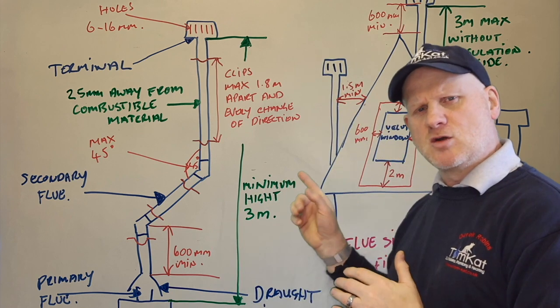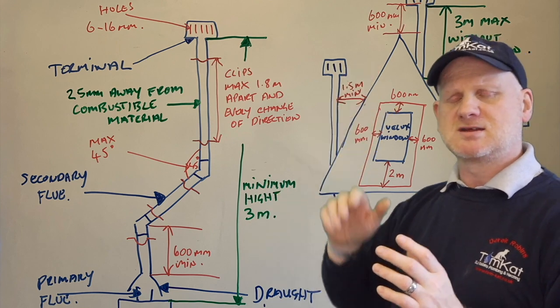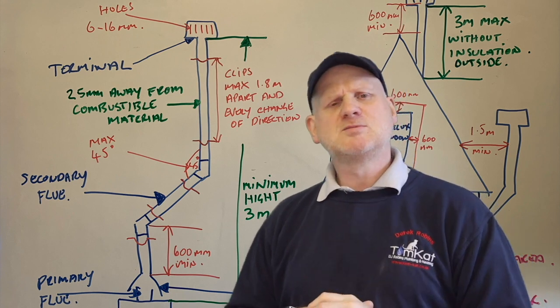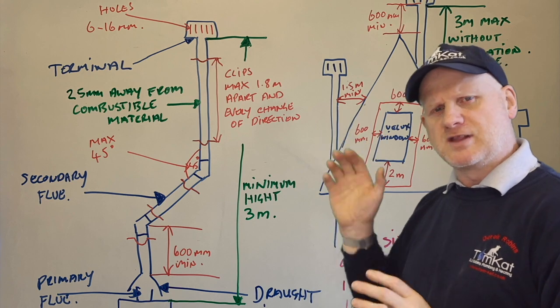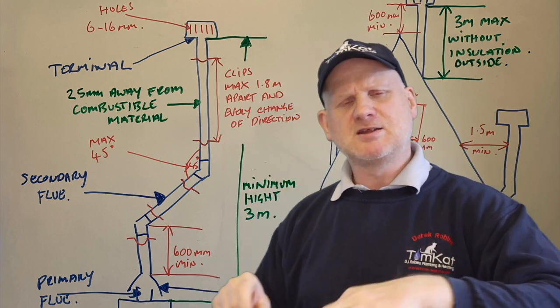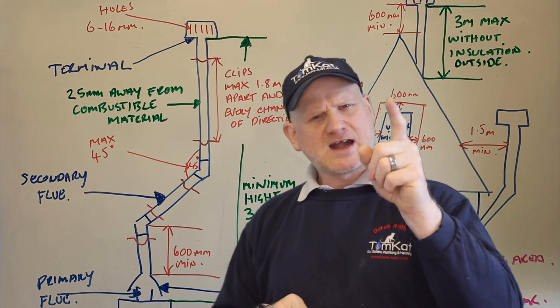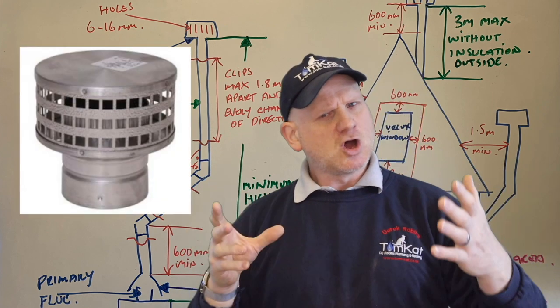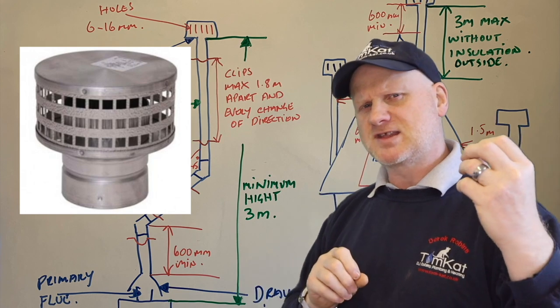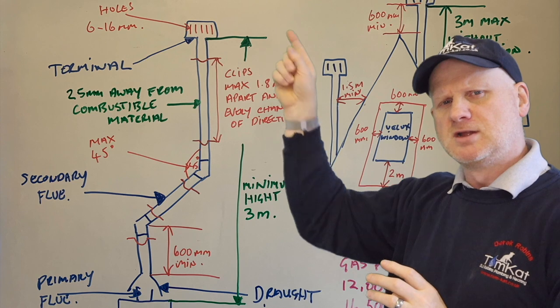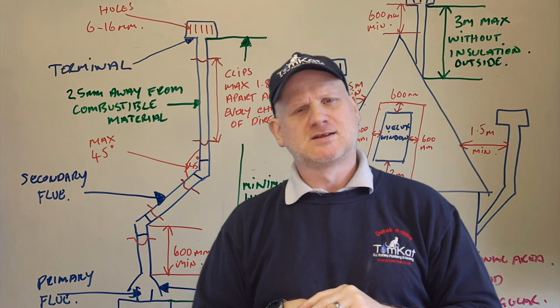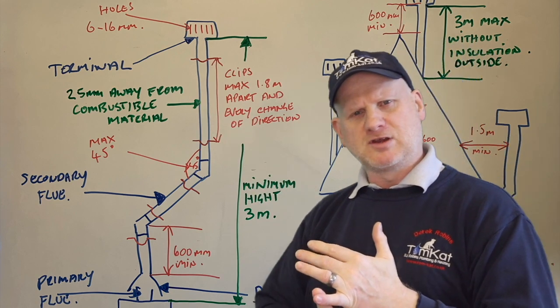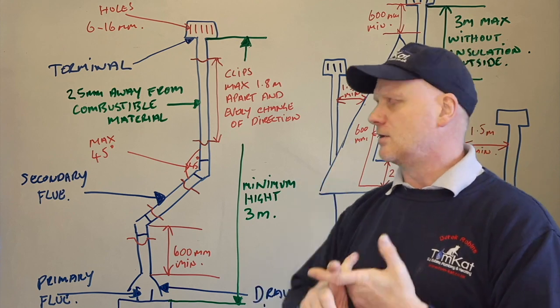The minimum height for an open flued appliance is 3 metres; the maximum height is per manufacturer's instructions. That's basically the secondary flue. Then attached to the secondary flue at the top is the terminal. The slots or holes in the terminal must allow the passing of a 6mm ball but not a 16mm ball. So the major components of this open flued boiler are: the primary flue, the draft diverter, the secondary flue, and the terminal.